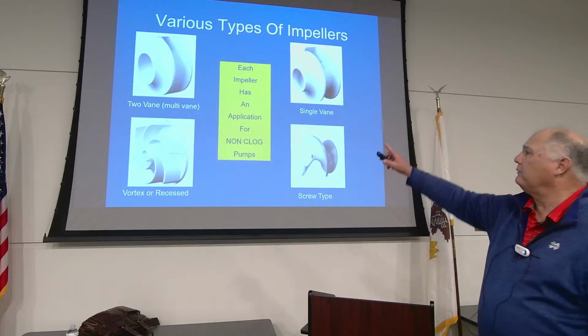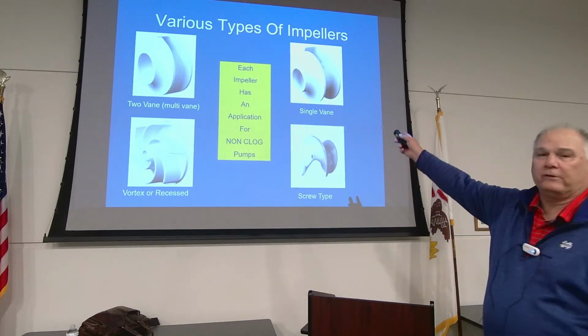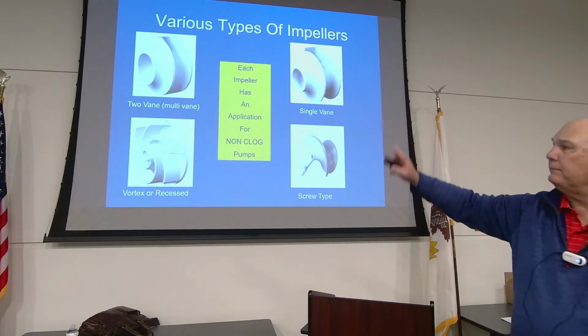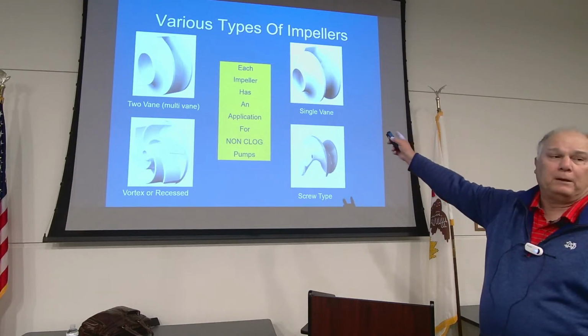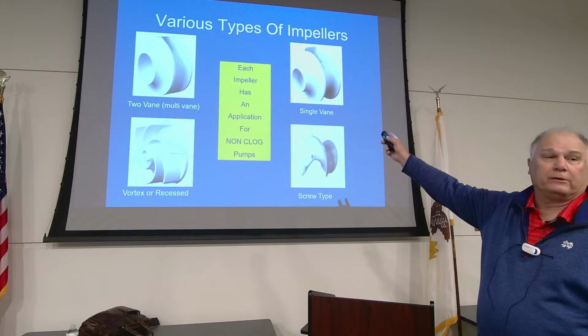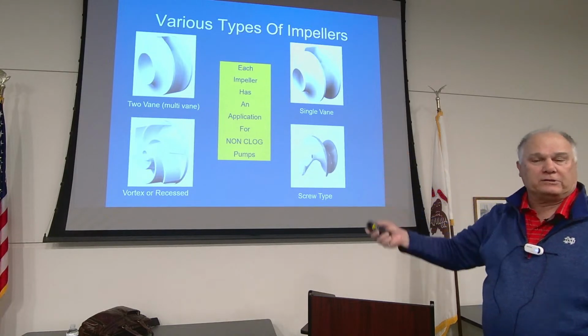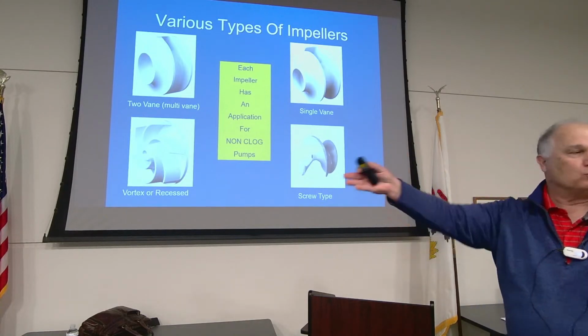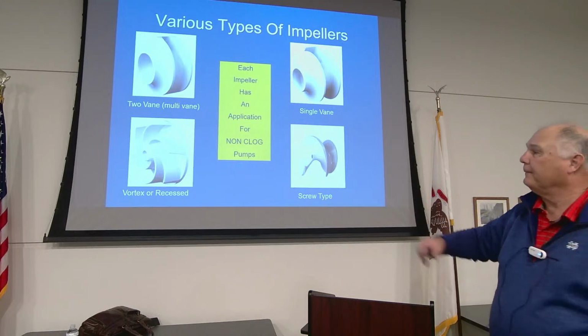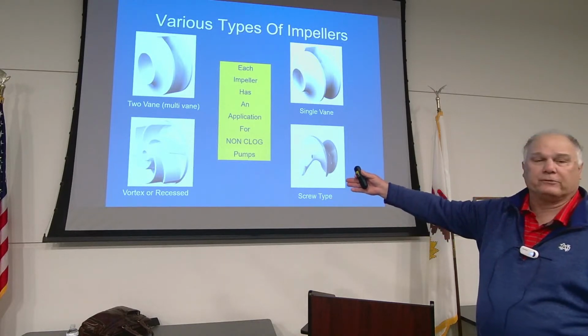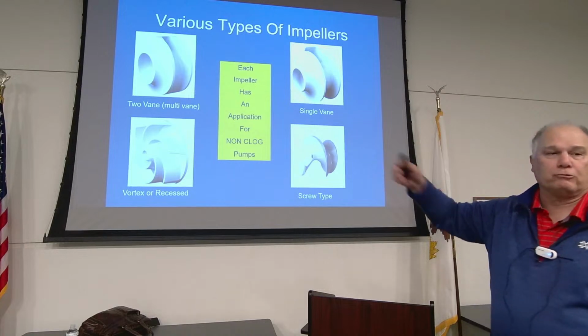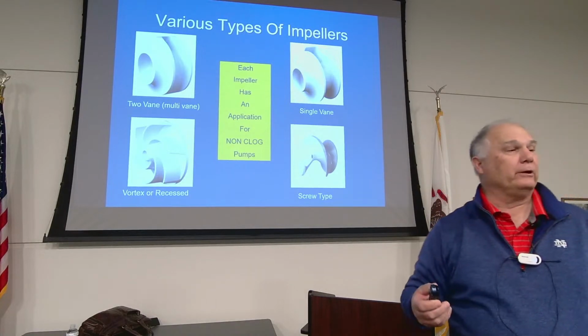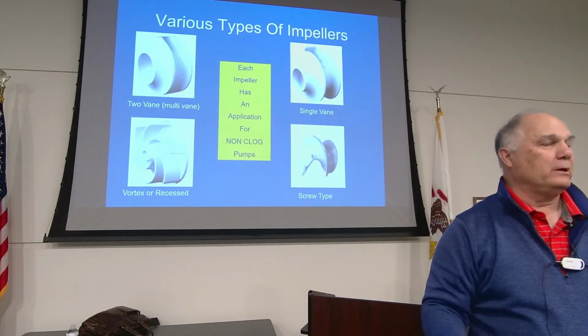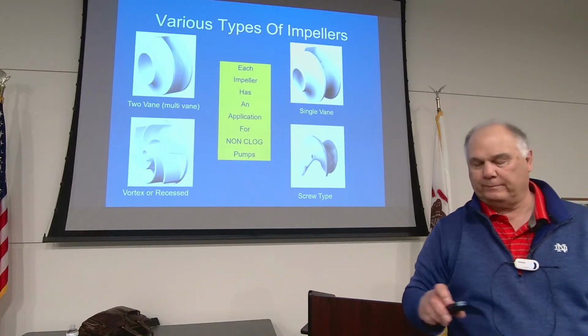So we have 2 vanes, and we have a single vane pump, which kind of looks like a one-armed bandit at a slot machine. That's a great pump, but it has to be operated in a very narrow condition because it's unbalanced, because it only has one arm out there. Then there's the vortex impeller pump, which is the very bottom left, and then a screw. A screw pump's a really good pump, but it has limited operations based on what you want to do.